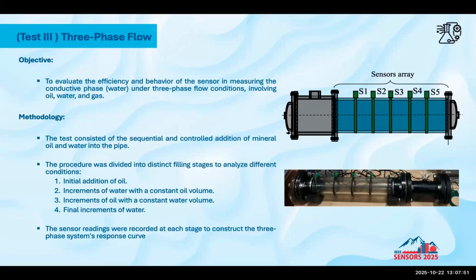So this is the last test. This is just to evaluate the efficiency of the sensor to measure the conductive phase, water, under three-phase conditions, in this case oil, water, and gas. So the conductive phase is just water. For that, we tested by sequentially adding controlled amounts of oil and water into the pipe. This is the same setup that we used in the first test.